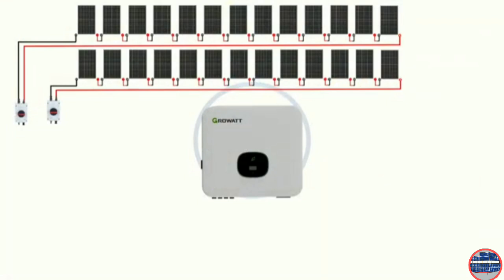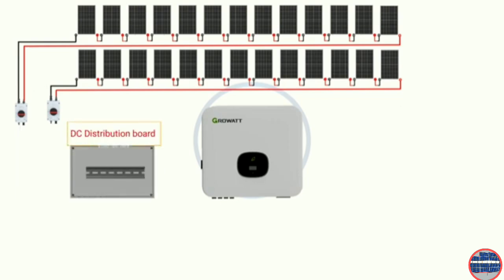DC isolator. A DC disconnect switch for a solar string is a safety device that allows you to manually disconnect the solar panels from the rest of the system. This is important for maintenance, repairs, or in case of an emergency. The switch needs to be rated for the voltage and current of the solar string. DC distribution board, DCDB.